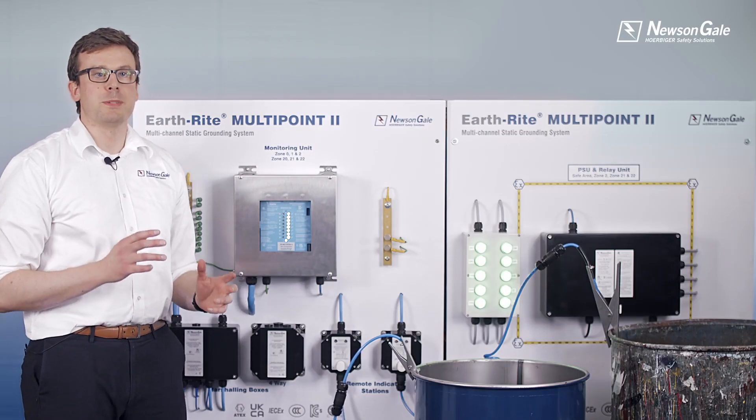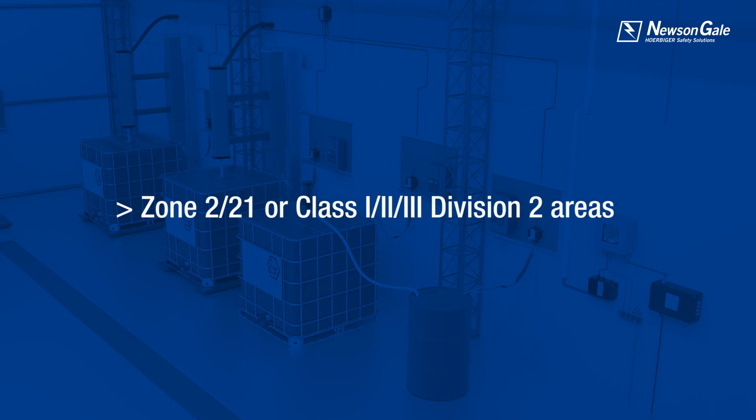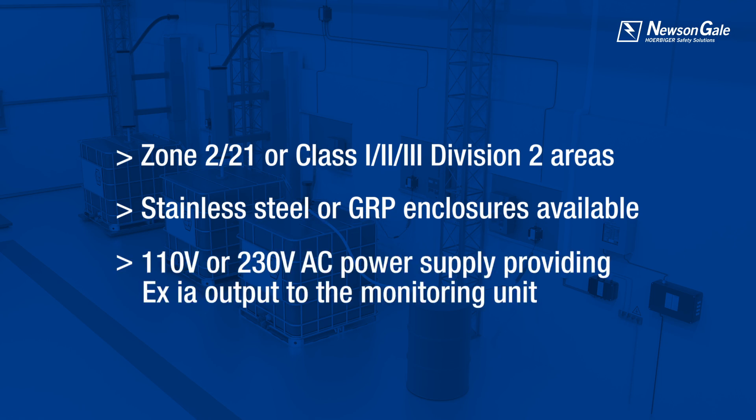The system is powered by a separate power supply module that can be located in a Zone 2/21 area or Class 1, 2, 3 Div 2. The power supply is available in stainless steel or GRP and is powered by 110 or 230 volt AC supply, which provides an Ex ia output to power the monitoring unit.